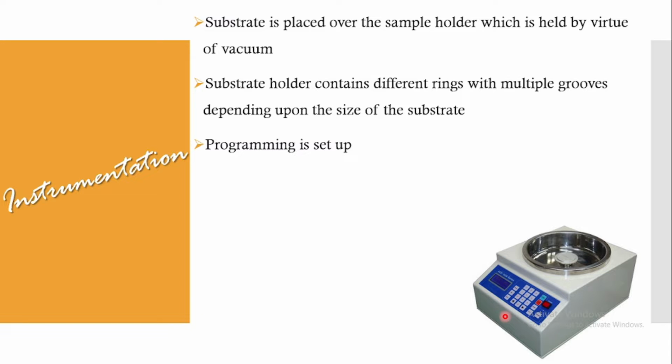And the second speed that we are going to set up, that is the acceleration while programming, is to dry off the solvent and to thin down the deposited film, based on which uniform spreading takes place on the surface. So the setting of acceleration is especially to give a higher speed step to ensure that the solvent can be evaporated. So it can be set up like 1000 rpm for 60 seconds, or the acceleration of 400 units, or the acceleration of 500 units, like that.